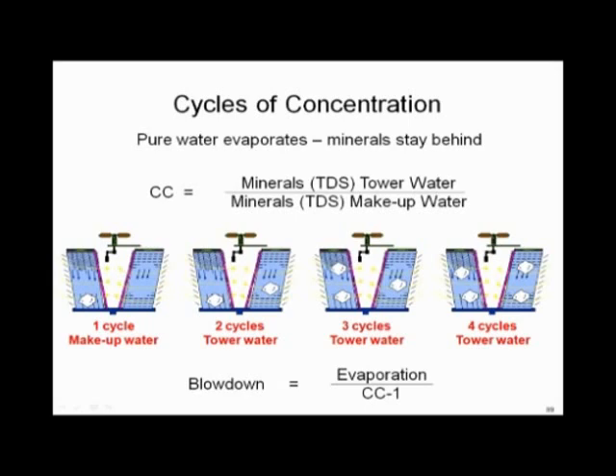If you've never really looked at cycles, this will help you understand what it is. Here's a formula for it — it's based on the blowdown rate of the tower versus the evaporation rate. If the blowdown rate is equal to the evaporation rate, you've got two cycles of concentration. We need to think about this because the code for the first time is specifying the cycles of concentration on your cooling tower, and you're going to have to deal with this.